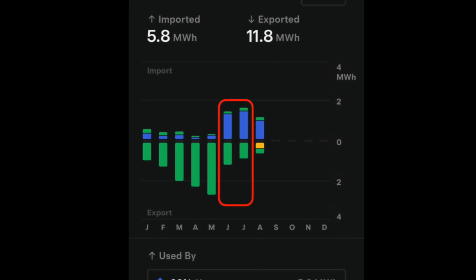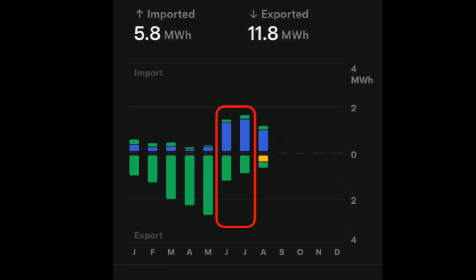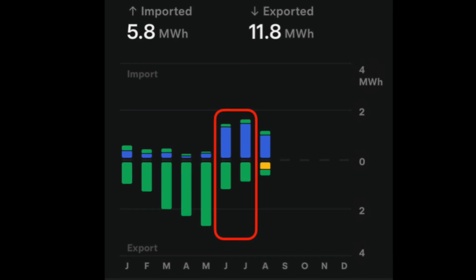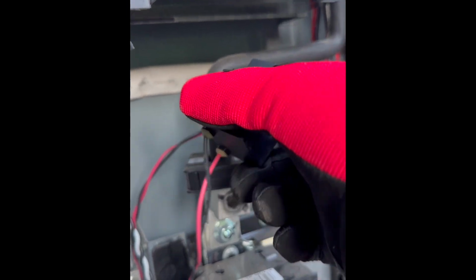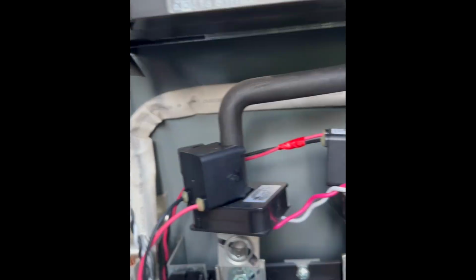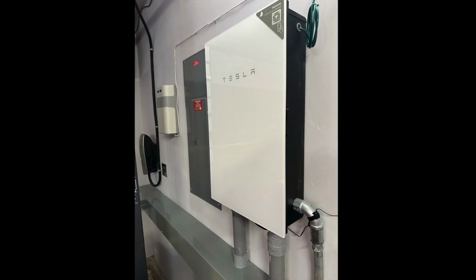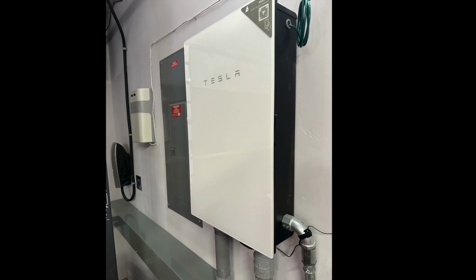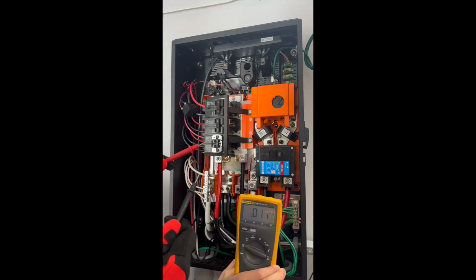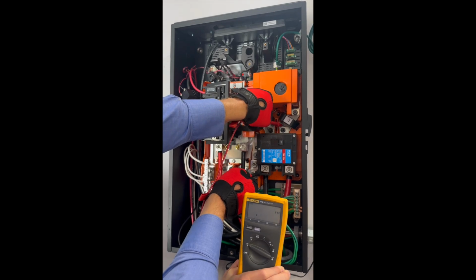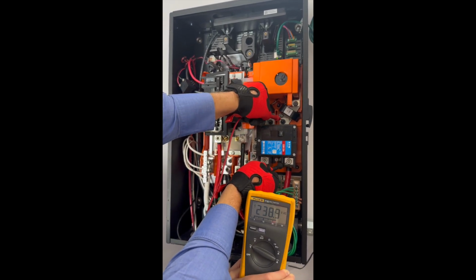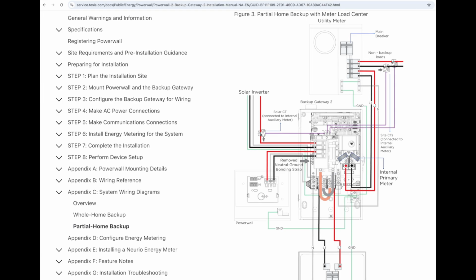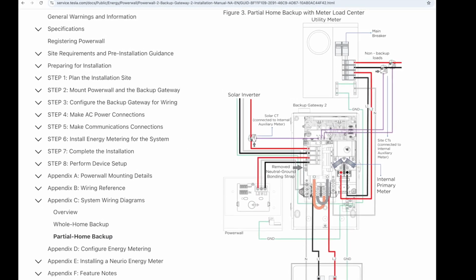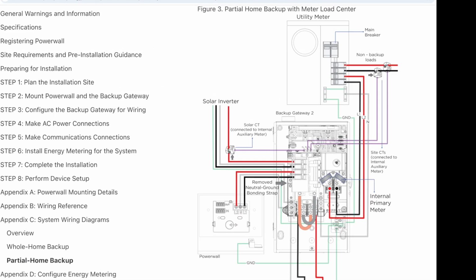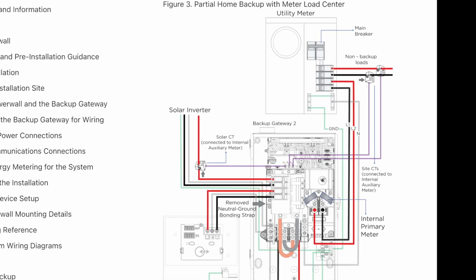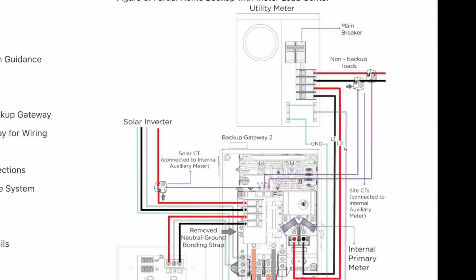My batteries still charged at unexpected and expensive times, and I was off when spot checking against my PG&E smart meter. So by turning my CTs upside down, the majorly obvious broken stuff was fixed. And for 3 months, I thought that maybe the other stuff was just a limitation of the backup gateway. Actually, until I started making this video in August of 2024, I didn't discover the full extent of my ignorance. My CTs actually hadn't been upside down, and we're about to get into why it kinda helped, but was the wrong answer.